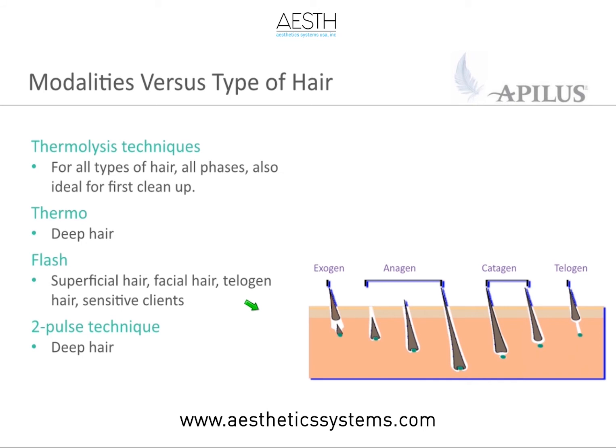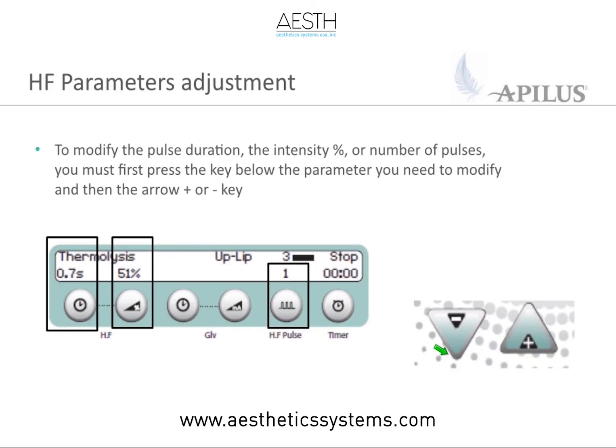You can use the multiple pulses to either deliver your current, your intensity in small increments versus just one big increment, or because you need to adjust your technique and do displacement in order to treat the bottom 2/3 of the follicle. So remember that you can adjust your pulses. So usually people will do double pulsing. So you can adjust your machine to do 2 pulses for you. Just hold down the foot pedal. And then if you use insulated probes, you can actually move and do displacement so that you deliver current down the bottom 2/3 of that follicle.